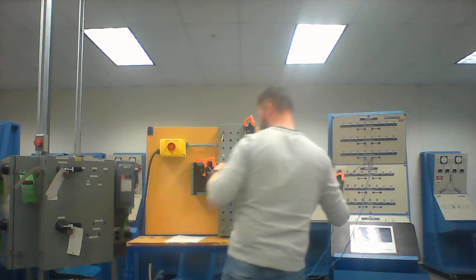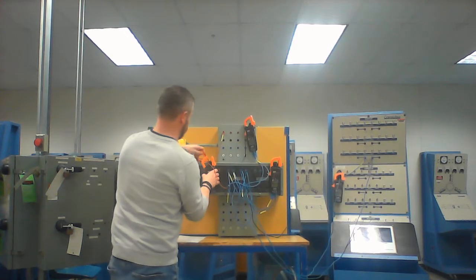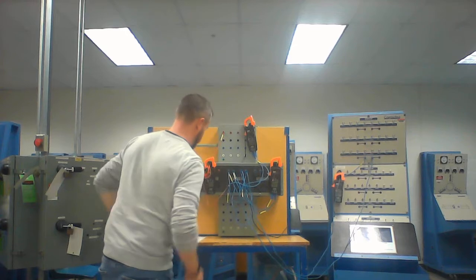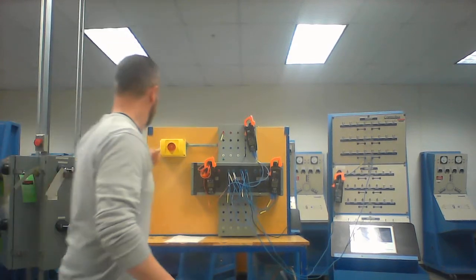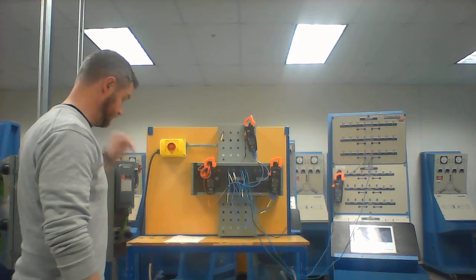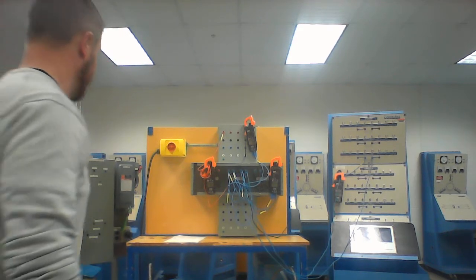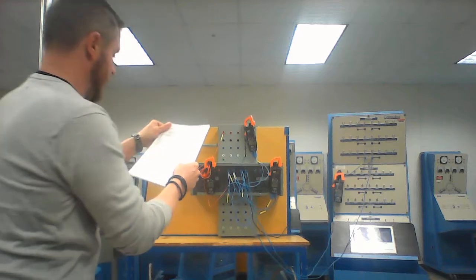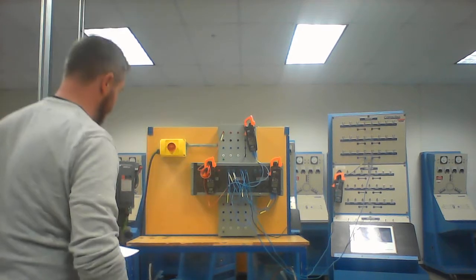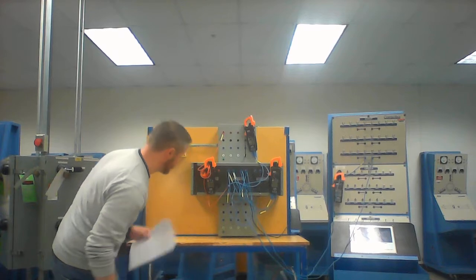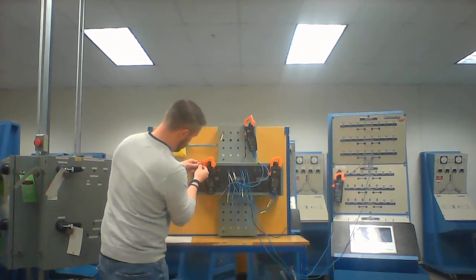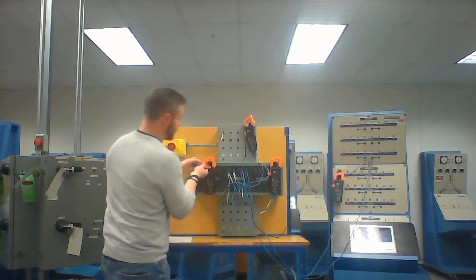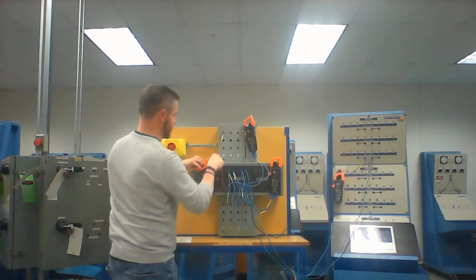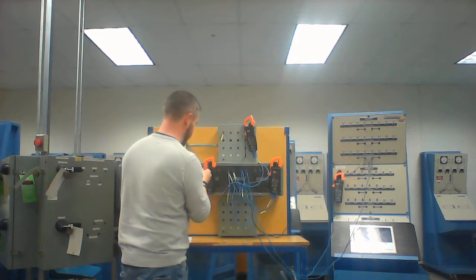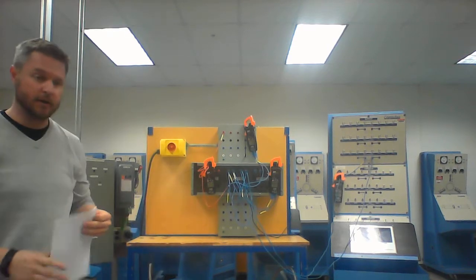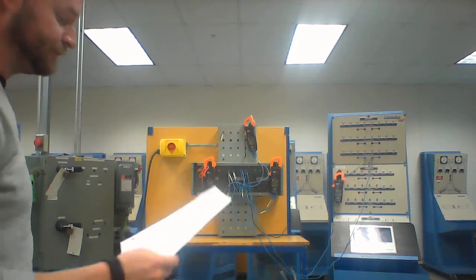Manual operation, meters are on, that's good to go. Excitation current. Ready to roll. Okay. Power on. Turn the power on and measure the excitation current in amperes. I am reading 0.72 with a 5 turn coil this time. Sorry, I missed one, now leave it at 5. Okay, 0.72 excitation, nothing connected just yet.